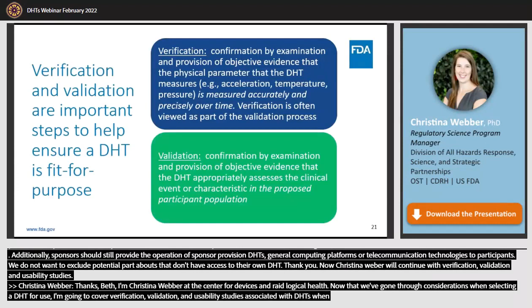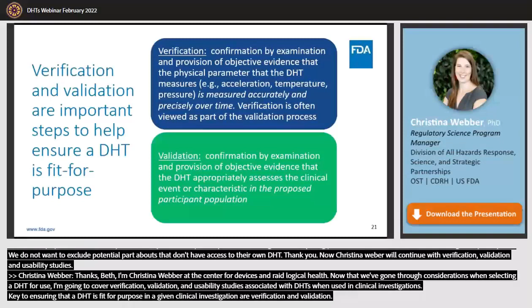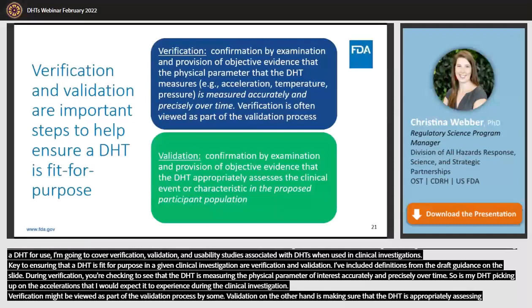Key to ensuring that a DHT is fit for purpose in a given clinical investigation are verification and validation. I've included definitions from the draft guidance on the slide. During verification, you're checking to see that the DHT is measuring the physical parameter of interest accurately and precisely over time. So, is my DHT picking up on the accelerations that I would expect it to experience during the clinical investigation? Verification might be viewed as part of the validation process by some. Validation, on the other hand, is making sure that the DHT is appropriately assessing the clinical event or characteristic in the clinical population of interest for the investigation.